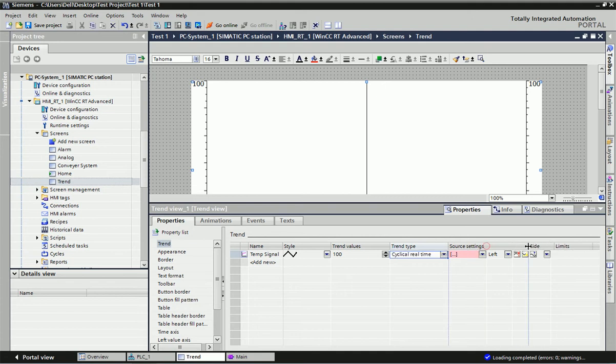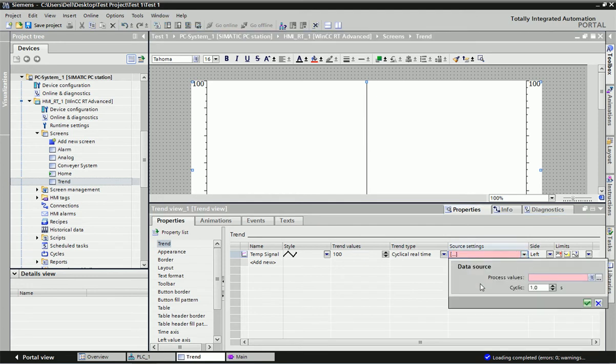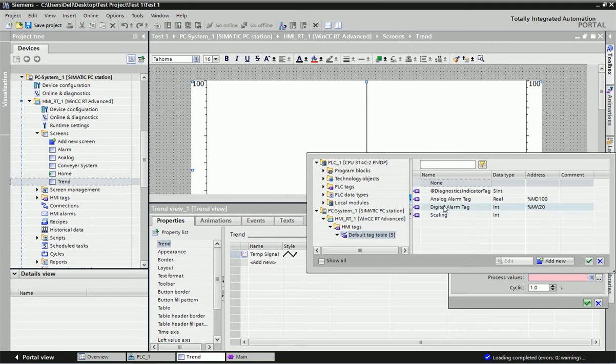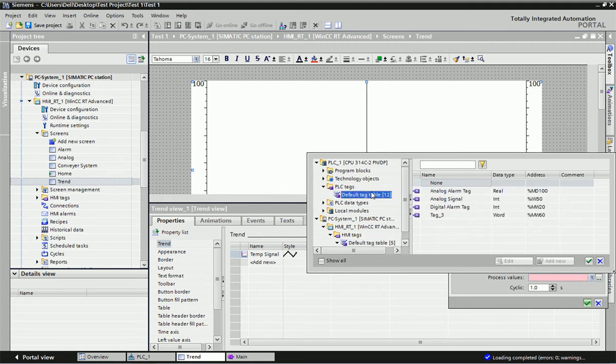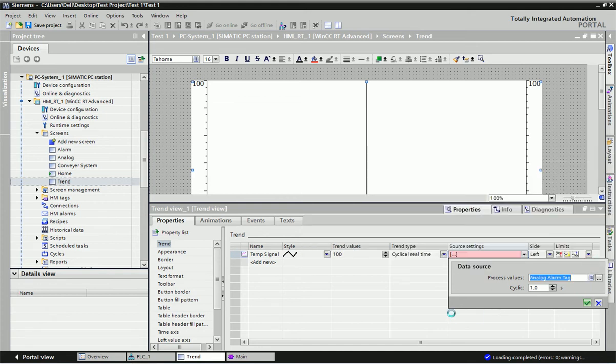Here is a very important part — the Source Setting. This is where you assign which tag the data is coming from. We go to PLC Tag because we want to configure MD100 data, which is the scaled output. I will assign this tag here and click OK. The data will update every one second, and you can change this cyclic time as well.